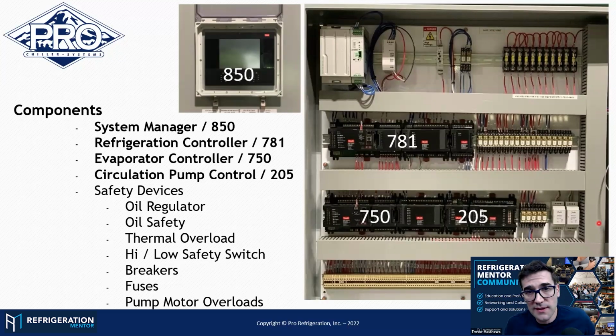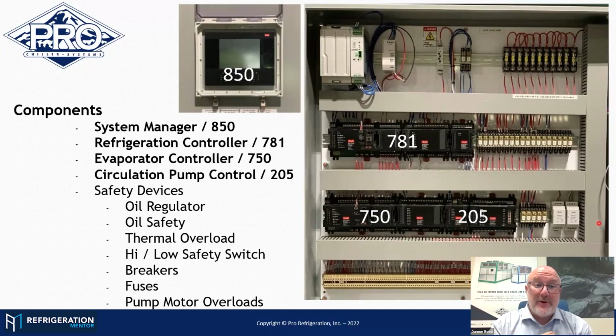And one quick tip with the new tools, and I know we talked about this before, is a thermal imaging gun. You go up to that panel and you see it's really hot on a couple of wires or on a contactor or something. There could be a loose wire there causing it. Yeah. From a tool standpoint, FLIR makes a thermal imaging camera that plugs into my cell phone, into an iPhone. You just pop it into the bottom and you can look at stuff.